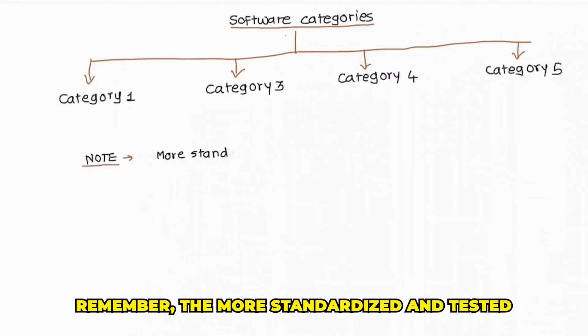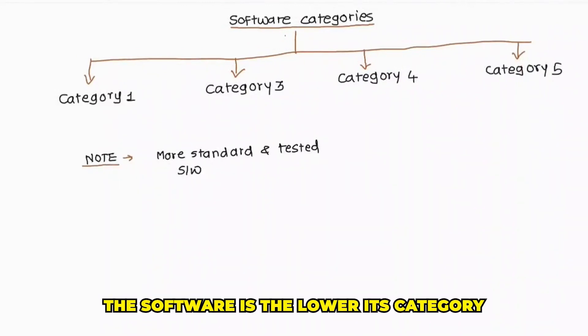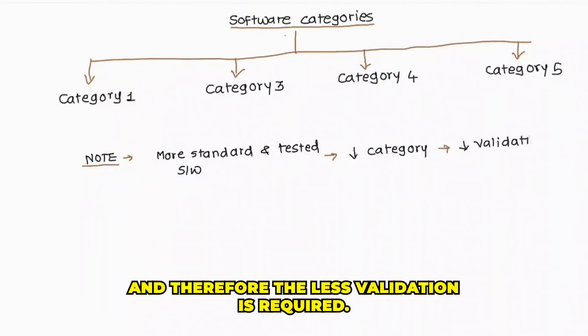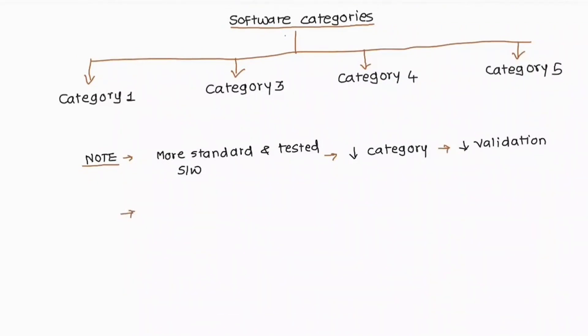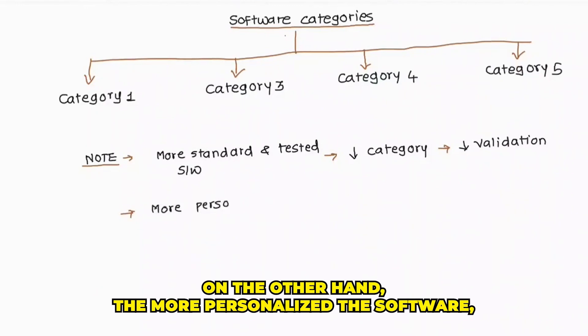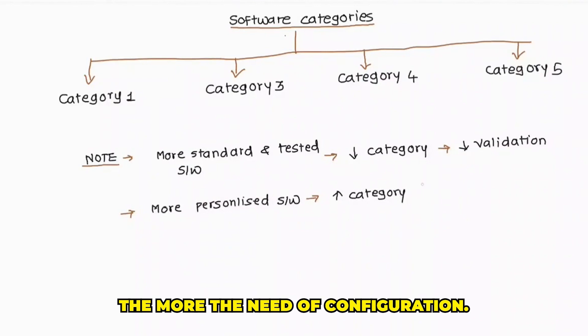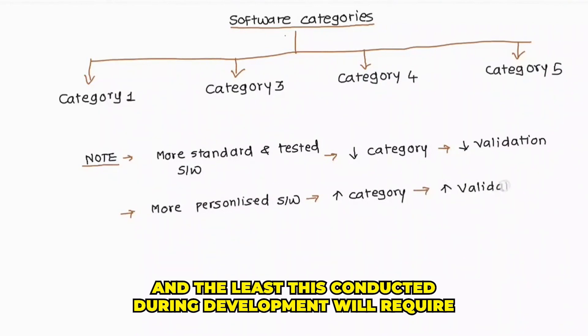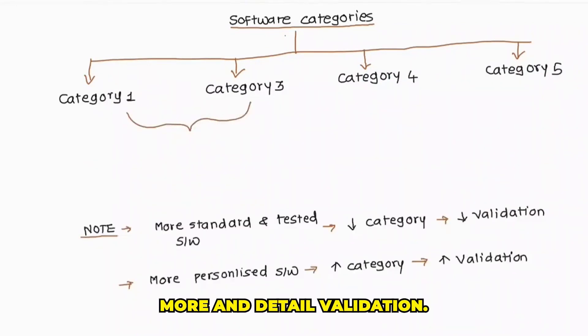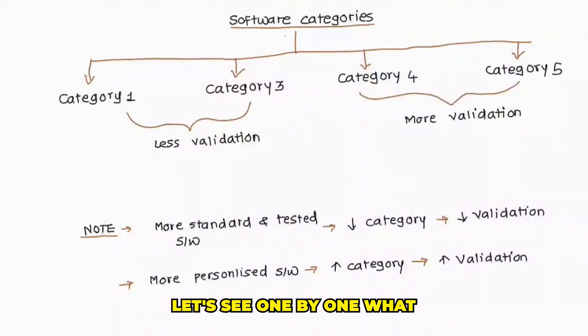Remember, the more standardized and tested the software is, the lower its category and therefore, the less validation is required. On the other hand, the more personalized the software, the more the need for configuration, and the least tested during development will require more and detailed validation.